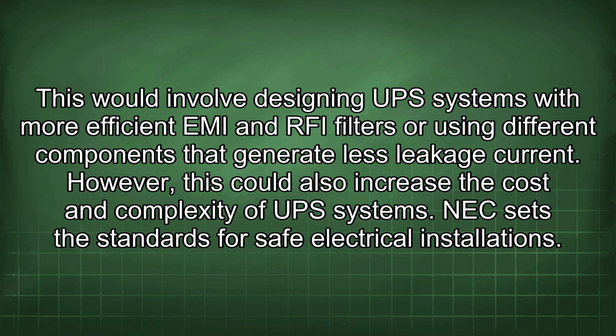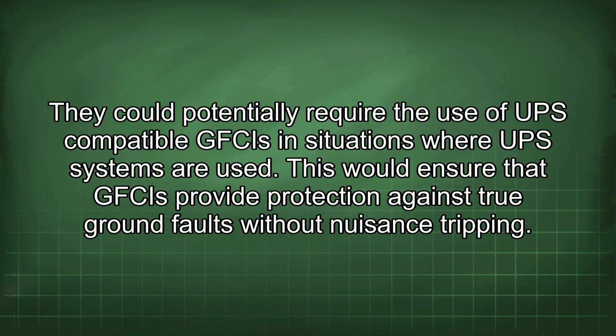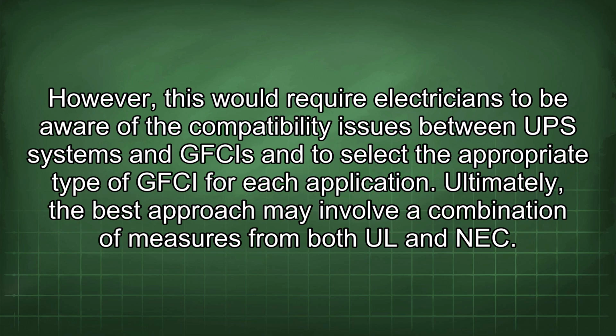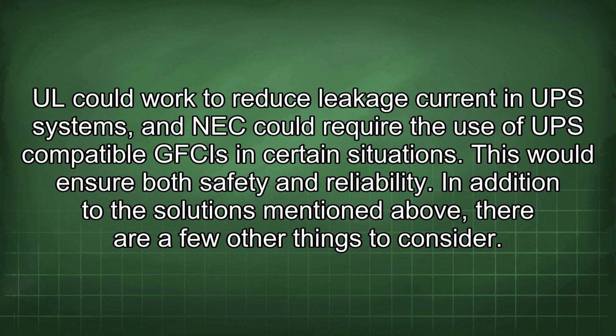NEC sets the standards for safe electrical installations. They could potentially require the use of UPS-compatible GFCIs in situations where UPS systems are used. This would ensure that GFCIs provide protection against true ground faults without nuisance tripping. However, this would require electricians to be aware of the compatibility issues between UPS systems and GFCIs and to select the appropriate type of GFCI for each application. Ultimately, the best approach may involve a combination of measures from both UL and NEC. UL could work to reduce leakage current in UPS systems, and NEC could require the use of UPS-compatible GFCIs in certain situations. This would ensure both safety and reliability.